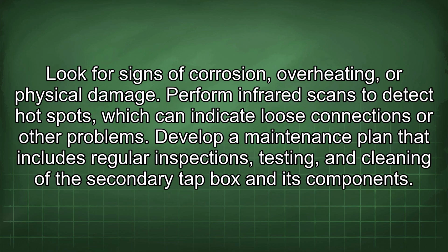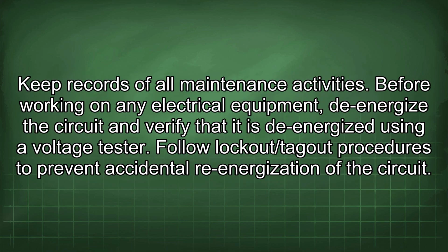Look for signs of corrosion, overheating, or physical damage. Perform infrared scans to detect hot spots, which can indicate loose connections or other problems. Develop a maintenance plan that includes regular inspections, testing, and cleaning of the secondary tap box and its components. Keep records of all maintenance activities.